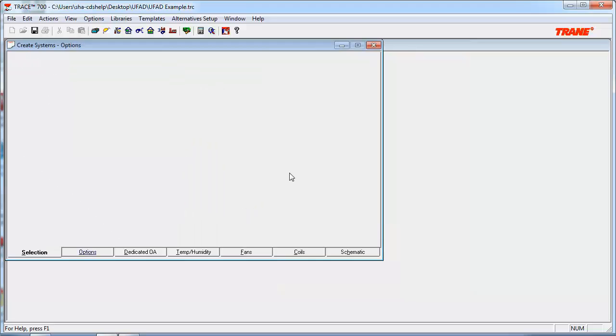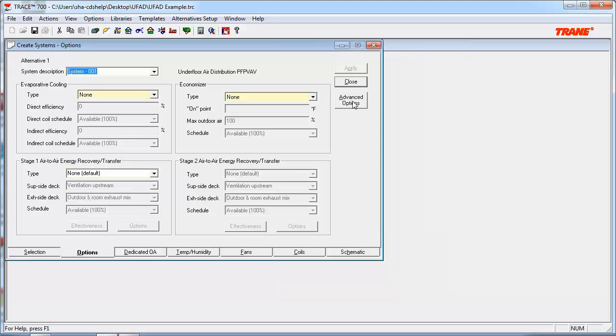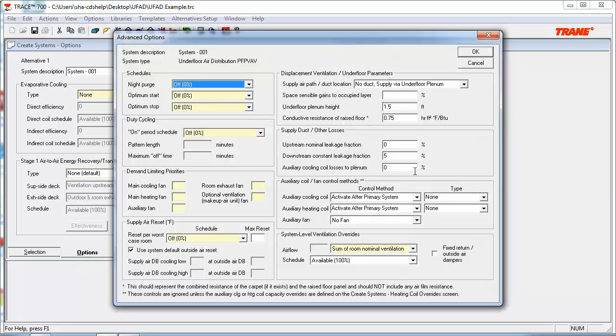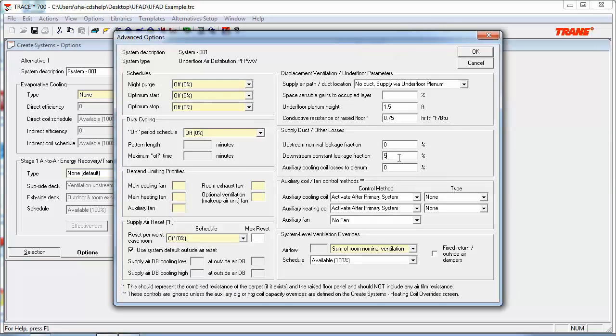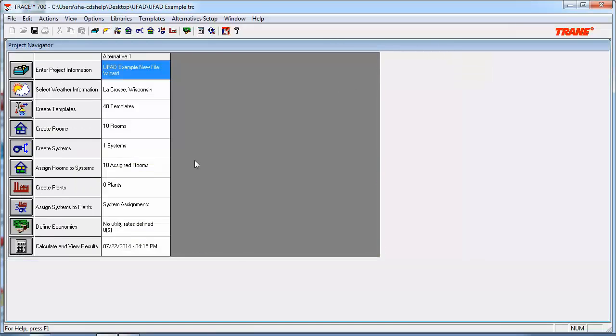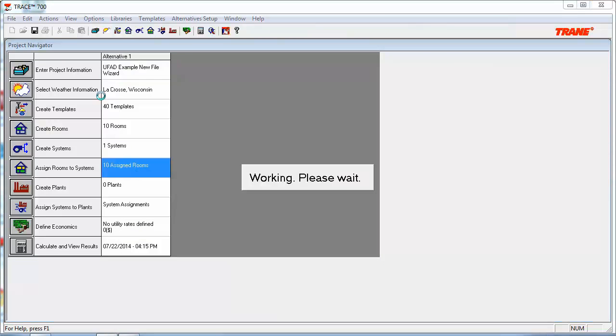Next, we can move on to the Options tab, and click the Advanced Options button. In this exercise, we're only going to adjust one thing here, and it's input a downstream constant leakage fraction to simulate some leaky underfloor plenums. So, in this case, I've already inputted 5% for our downstream constant leakage fraction. Once that's set, we can hit OK. We can go ahead and close out of Create Systems.